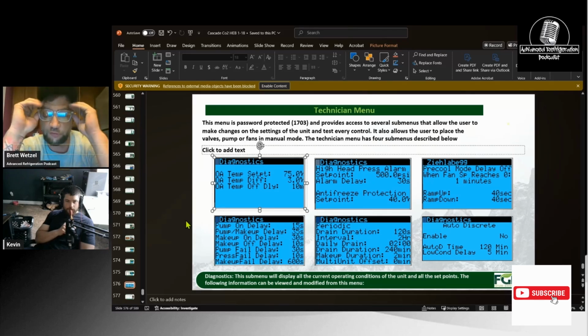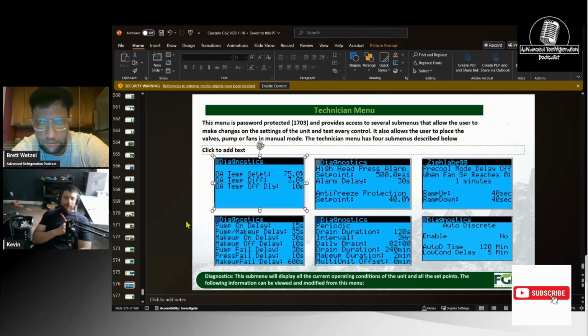One of the other options that this tower, or the BAC gas cooler, does have is you can actually run the fans backwards to try to push out the debris, which everybody does. Everybody's tried that. I've never ever seen it work. I think if you had the pre-pad, like on the Munters unit, they have that black filter material. That would be awful. Those things plug up so much.